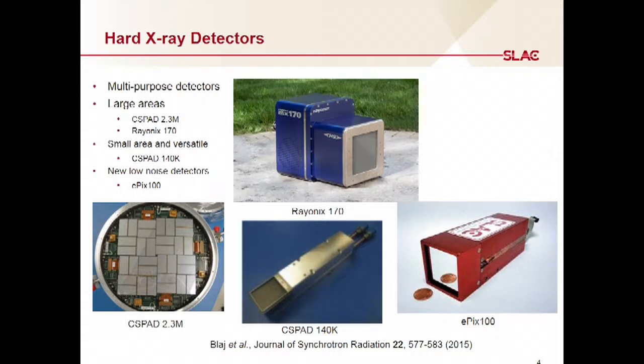I will also briefly talk about the X-ray detectors that we have. There are lots of X-ray detectors available, but only a few of them are really suitable for FEL science. Usually the capability we need is a high repetition rate, and a lot of CCDs do not operate at the 120 hertz rate that can really take advantage of our repetition rate. So we have specially developed detectors that were built for us, such as the CSPAD. This is a 2.3 megapixel detector, which can run at 120 hertz.